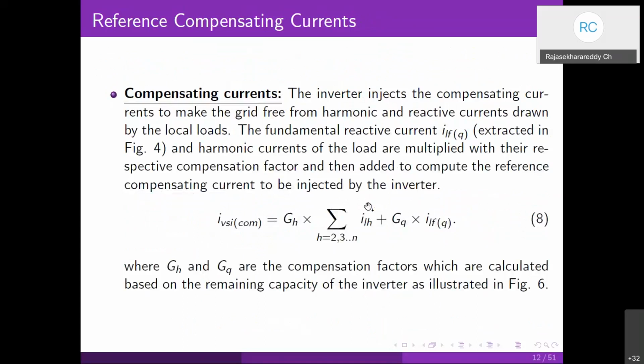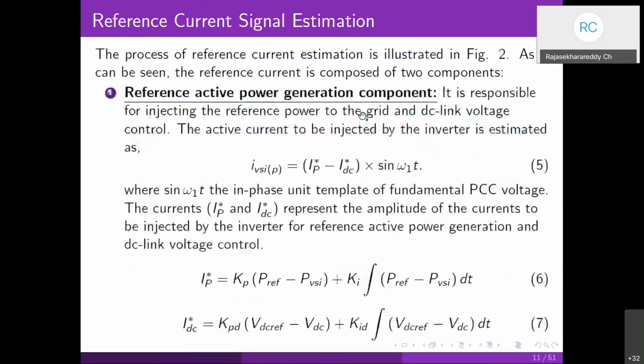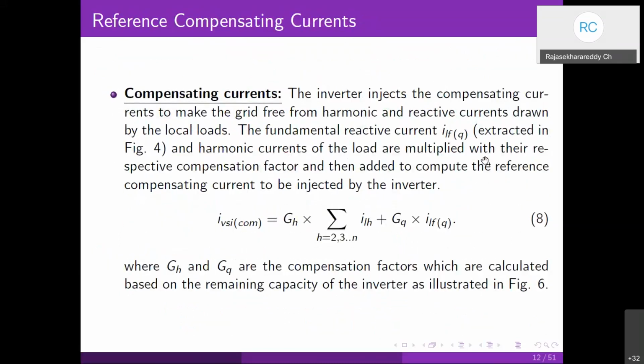And the other part of the reference current signal is the compensating current. The voltage source inverter injects the compensating current to make the grid free from the harmonic and reactive currents drawn by the local loads. The fundamental reactive current ILFQ is extracted in figure 4. The harmonic components of the load current are multiplied with their respective compensation factors and then added to get the reference compensating current to be injected by the inverter. So we take those reactive and harmonic currents of the load and multiply them with GQ and GH respectively, so that we get the compensating current to be injected by the voltage source inverter.